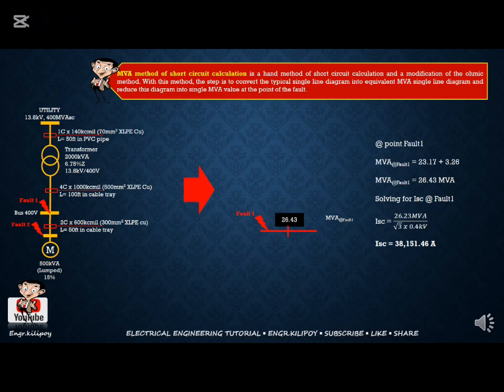So to solve for the short circuit current, yung simplified MVA fault at fault 1 divided by square root ng 3 divided by yung bus voltage dun sa bus under analysis. In this case, fault point 1, mapapansin mo dito nasa 400 volt bus siya. So ang ating voltage yan is 0.4 kV. So with the equivalent short circuit of 38.2 kilo ampere.